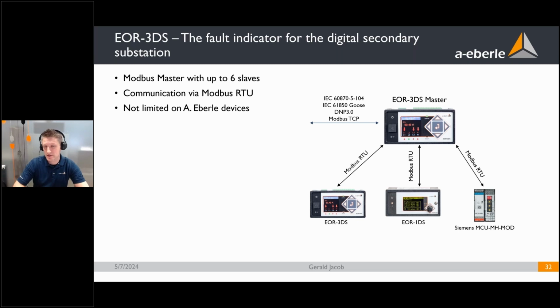Yeah, as I said, it's not limited to Eberle devices. It makes maybe no big sense, but you could also read out other EOR-3DS devices. You can read out EOR-1DS devices, or you can connect any other Modbus RTU speaking device, for example, a Siemens motor control unit, which is also available with a Modbus interface. This could also be connected here.